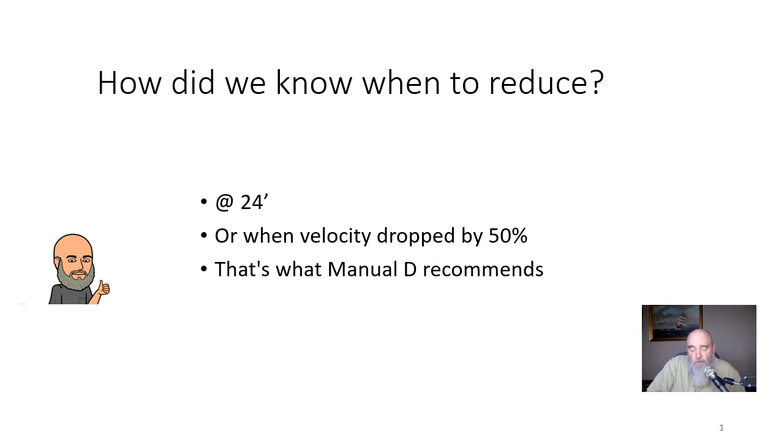You can follow the rules as per Manual D and reduce as many times as you want, but reducing as per Manual D is exactly what's on your screen: at 24 feet or when your velocity has dropped by 50 percent. You can go years back with Manual D and it was much more stern with that guidance. In the last printing it's turned into kind of around 24 feet and kind of around when your velocity drops to 50 percent, but it's not nearly as strict.